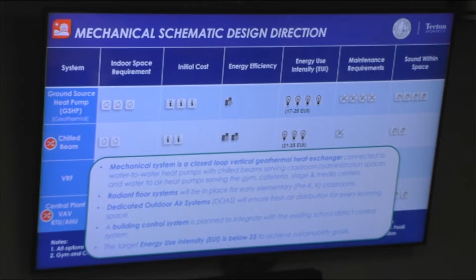And if we're still a pretty good EUI, if you look at chilled beam it's 21 to 25, very good low EUI versus the ground source heat pump at 17 to 25. So we're still in a good range. It's really going to come down to how our schematic estimates come in, and we can make an informed decision. But we're recommending, no matter what we do, we use chilled beam as our basic design and use air handlers or heat pumps for the gym and cafeteria.